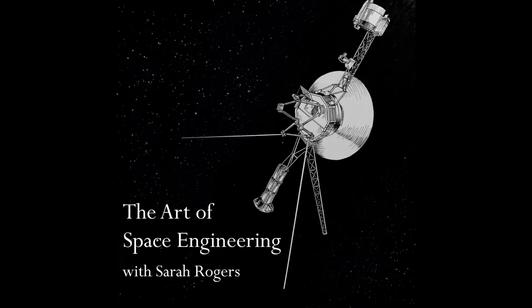and we characterize the resolution of a spectrograph by this thing called the R factor. And the R factor is, at any given point in the spectrum, the wavelength of light at that particular point divided by the smallest resolution element that you can resolve in the spectrum. So it's lambda over delta lambda. And, you know, so low resolution systems have an R of a few hundred. High resolution systems have tens of thousands of resolution elements at a particular wavelength.